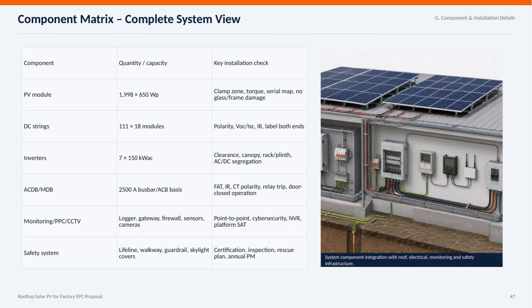Here we have a comprehensive component matrix providing a complete system view of the rooftop solar PV setup proposed for the factory EPC project. The key components include nearly 2,000 PV modules, each rated at 650 watts, carefully installed with attention to clamp zones, torque specifications, and damage prevention. Moving on, the DC strings consist of 111 strings with 18 modules each, where we ensure correct polarity and proper labeling for safety and efficiency. The system includes 7 inverters, each with a capacity of 150 kilowatts AC, requiring appropriate clearance and segregation between AC and DC parts to maintain safety and performance.